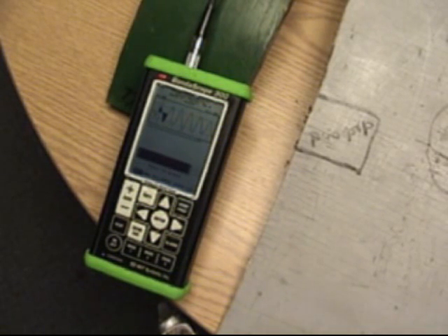Again looking at a good area, bad area, you kind of set the frequency and the gate and the alarm level and any gain. And if you're looking at amplitude set the gain for the alarm threshold and you're ready to go. So if you have any questions feel free to get a hold of myself or Greg.